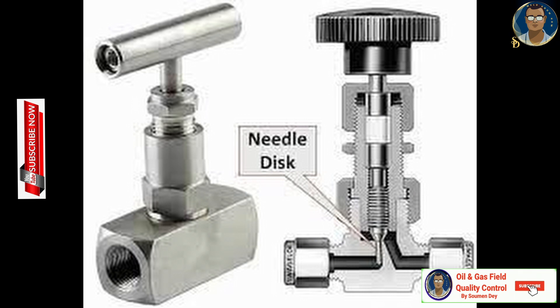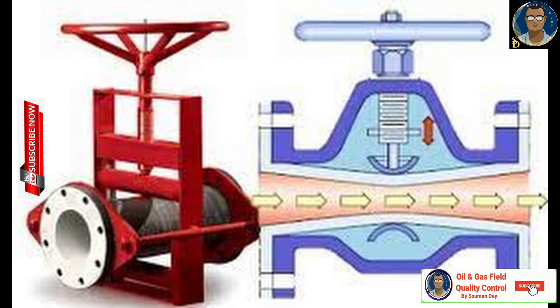Needle valves are mostly used in small diameter piping systems where fine and accurate flow control is needed. The needle valve gets its name from the point on a conical disc used within it. Pinch valves are mostly used for handling solid materials, slurries and liquids with suspended solids. These valves use a linear motion and feature an internal sleeve to isolate the media.